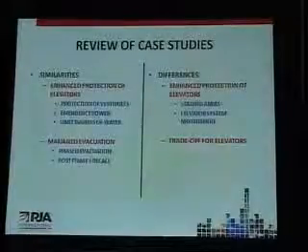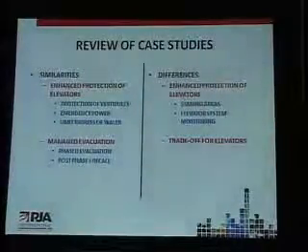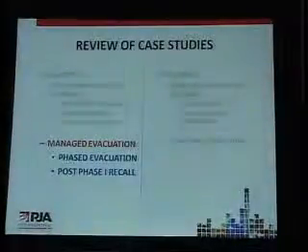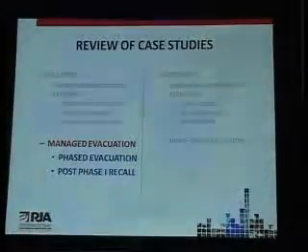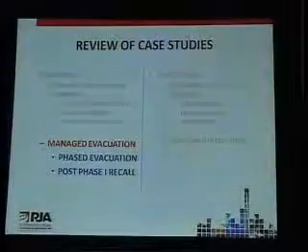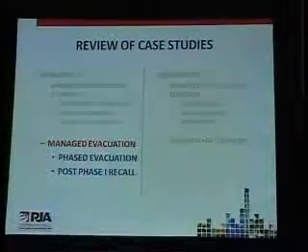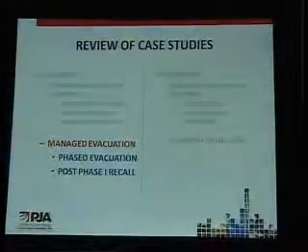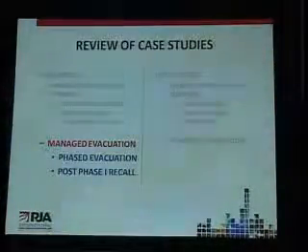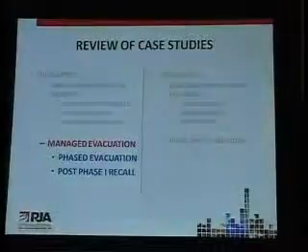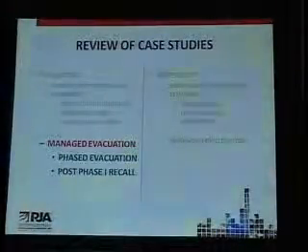in these buildings. One thing that I want to point out, though, one of the biggest similarities that you'll see is that all of these case studies used managed evacuations and are planned to have phased evacuations, where in a normal alarm we're only going to evacuate 3 stories, maybe 5 stories at most, going down to an area of refuge where they'll wait until the alarm gets cleared, the fire gets extinguished.